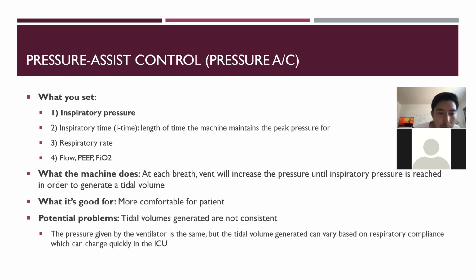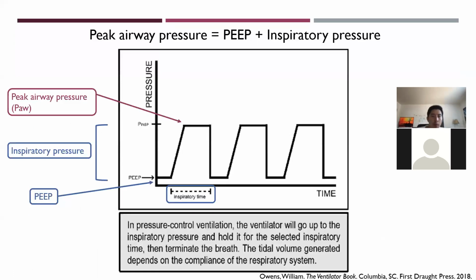So, potential downsides of pressure assist. This is what I was talking about here. The ones in blue are the ones that you will be setting. So I set my PEEP, like my baseline expiratory pressure. And what I mean here is that you're going to set this difference here, the inspiratory pressure. So let's say my PEEP was 5, and I say I want an inspiratory pressure of 20, and the machine will raise the pressure by that much. And also the inspiratory time, which is how long the machine is going to hold when it achieves the inspiratory pressure that you set. So you do not set the peak airway pressure in this mode. All you're setting is these two, and in a situation where things are working great, there are no complications, your peak airway pressure, the maximum pressure, will equal your inspiratory pressure plus your PEEP. Does that make sense? I feel like this was kind of hard for me to wrap my head around.